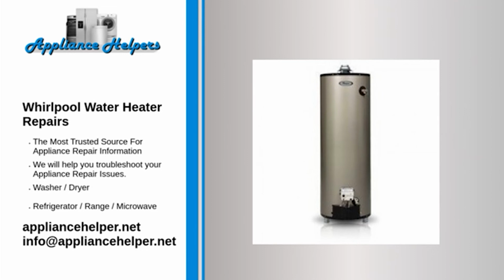Water leaks. With a new water heater, most leaks are caused by leaking connections at the hot water outlet or cold water inlet. Occasionally, leaks can be found coming from a fitting such as around the temperature and pressure relief valve or around one of the heating elements. Leaking fittings can often be tightened or repaired. It is extremely rare for a new tank to leak.